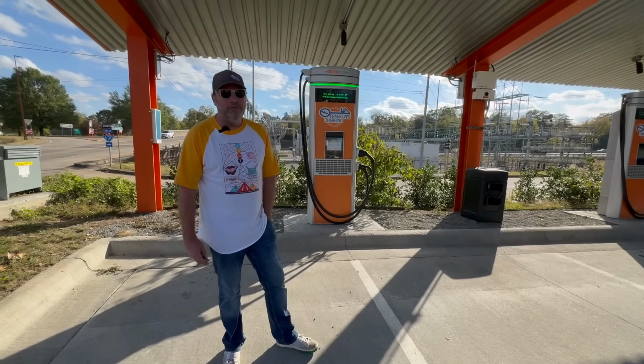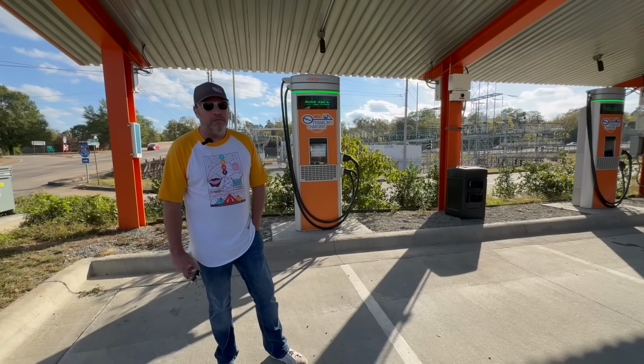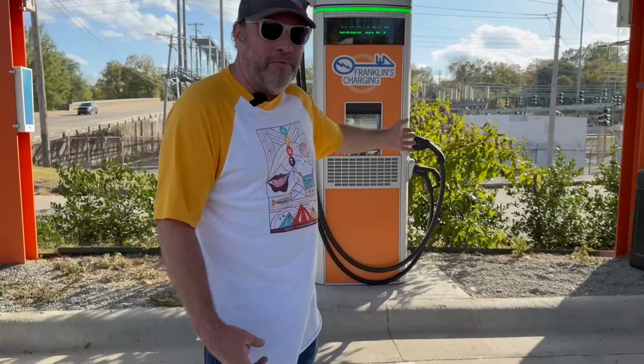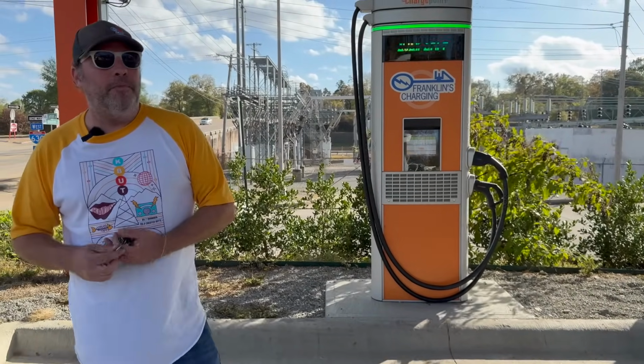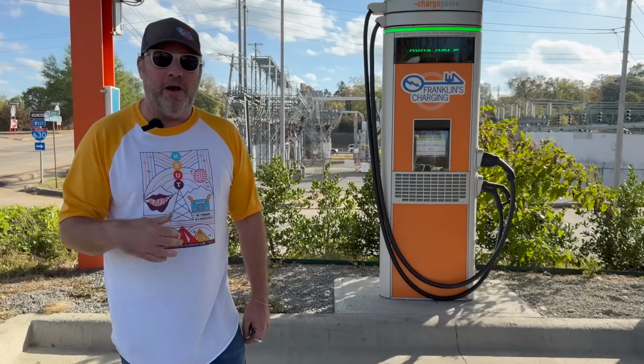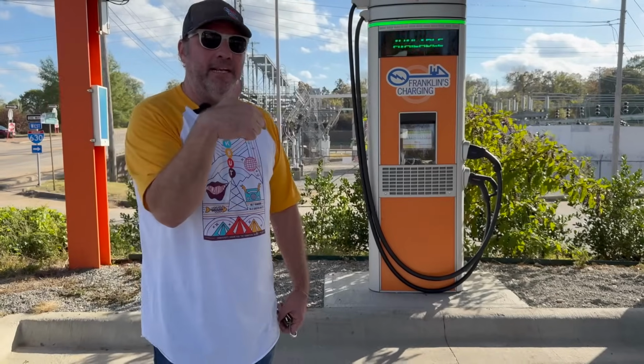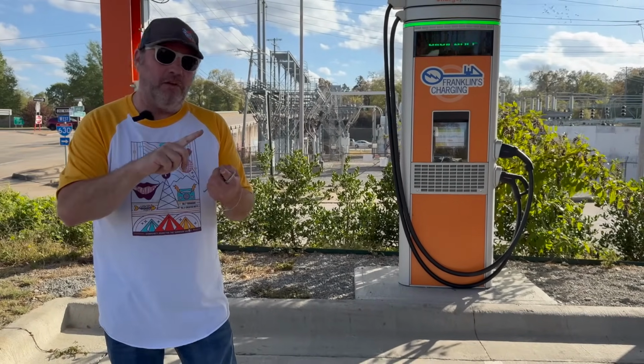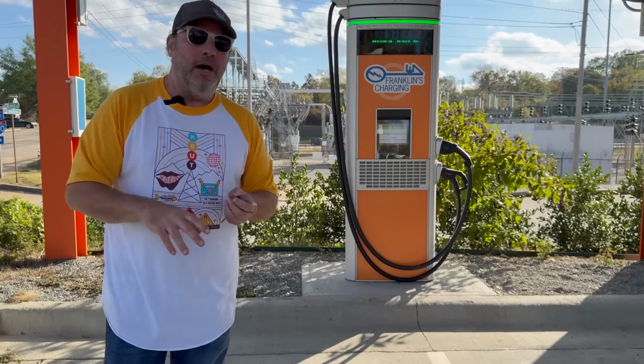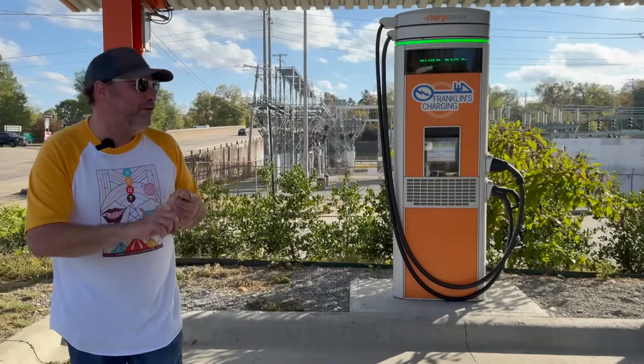We've alluded to demand charges a lot. Just at a high level, your per kilowatt hour rate's really cheap, right? Right. But can you explain to our audience how the demand charge works roughly? So in commercial installations, and this isn't just isolated to Entergy, our provider, or Arkansas, or anything like that, they take your peak demand at whatever point you hit that during the month. So what's your highest kilowatt? So that would be everything ripping here, basically. Right, everything plugged in and going, and they base what's called a demand charge on that. So that is a huge hit every month on a bill, which we won't get into dollar amounts because I'm sure Entergy already loves me and I don't want to alienate them any further.